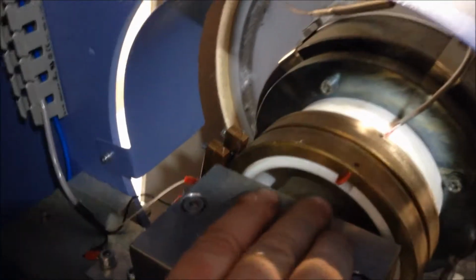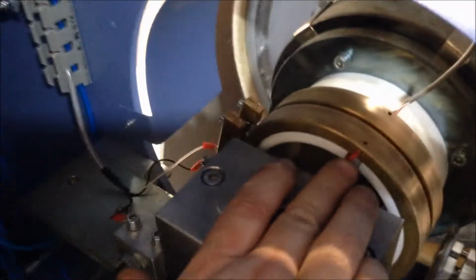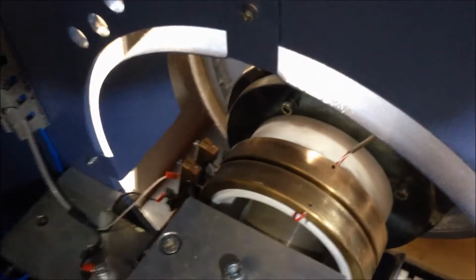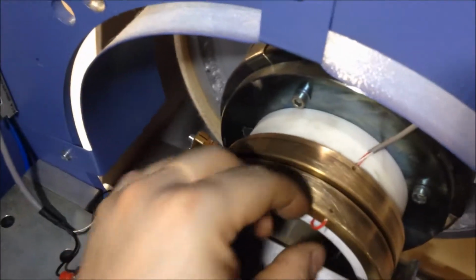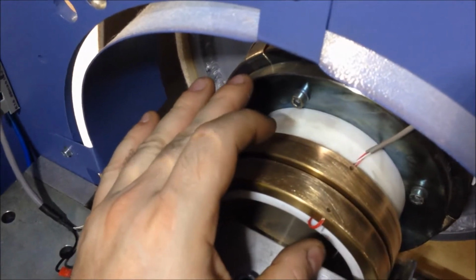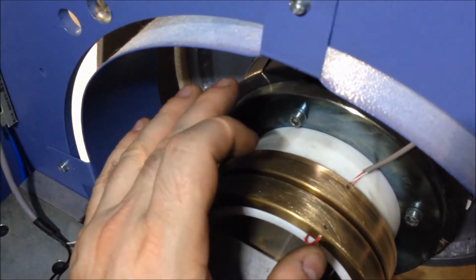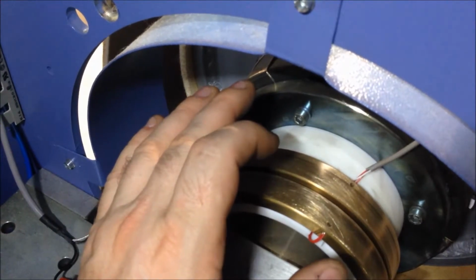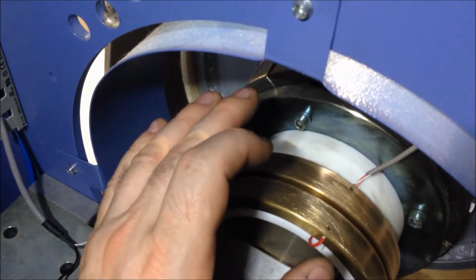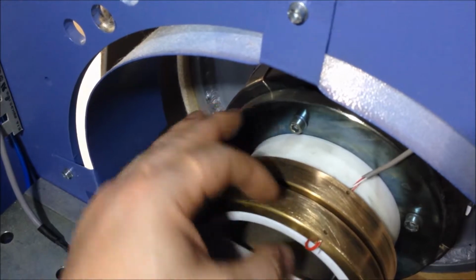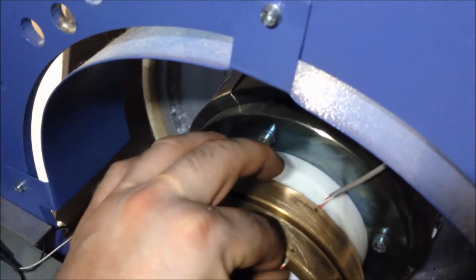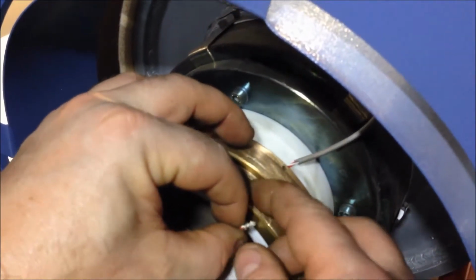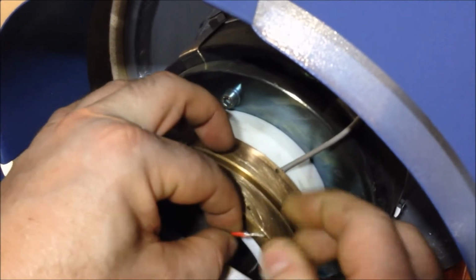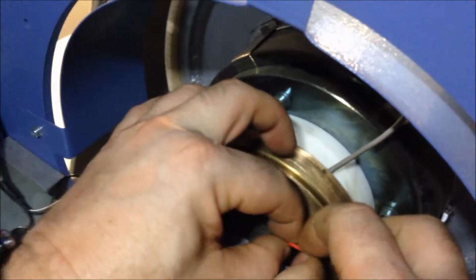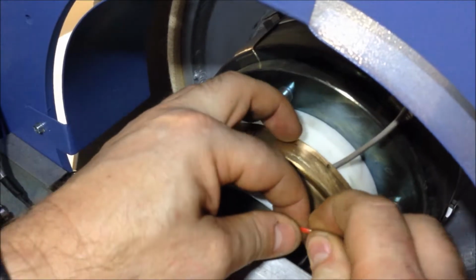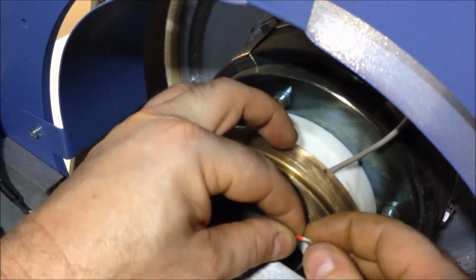But for now, what we have is this thermocouple wire, and when our temperature is fluctuating above and below our set point, and also even alarming out sometimes, the first thing I do is check to see if my wires are tight, which this one is not. What the heck?